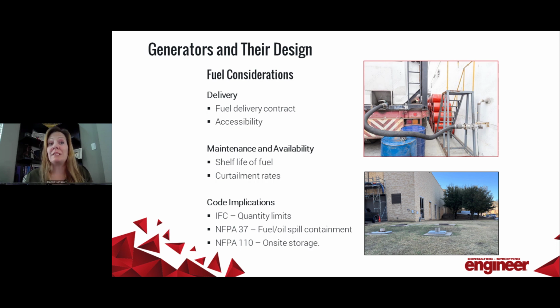Diesel has it, and it basically will deteriorate if stored for over 1 year. So when high capacity tanks are used and the fuel isn't necessarily always cycled through, the fuel definitely needs to be periodically drained and replaced with fresh fuel. Of course, that's quite costly. You're not just going to dump the fuel. That's not possible, but they do offer fuel polishing systems that can be used to clean the fuel.